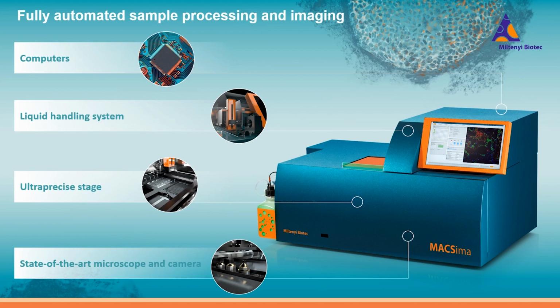And then the stage is driving to the state-of-the-art microscopes and cameras, and this microscope consists of 2x objectives to at first take an overview of your image. There you can then select the region of interest, and then you have 2 20x objectives that give you in the end a single cell resolution of your tissue samples or your cells. And all of this is happening fully automated. So you put in your antibody panel as well as your samples, you press play, and then you can go on with your day.